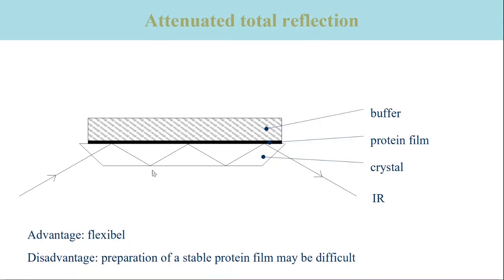The next slide illustrates the technique of attenuated total reflection, which is commonly abbreviated as ATR. A sample film is prepared on an infrared-transmittent crystal. A buffer is placed on top of the film. This is usually only possible for membrane proteins, because only they attach relatively firmly to the crystal.